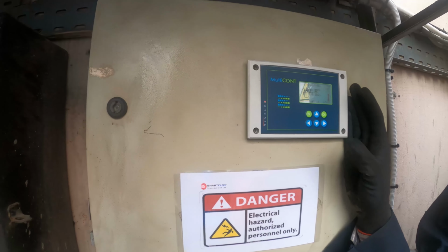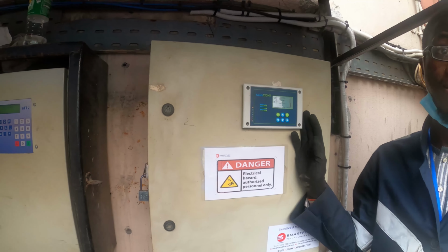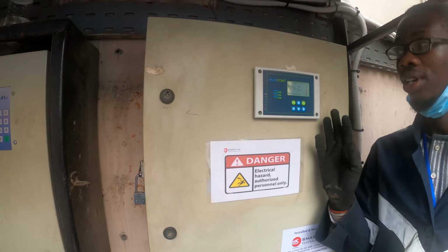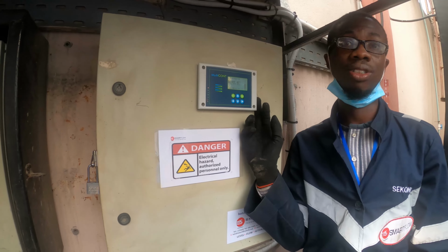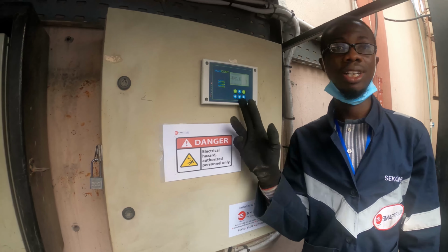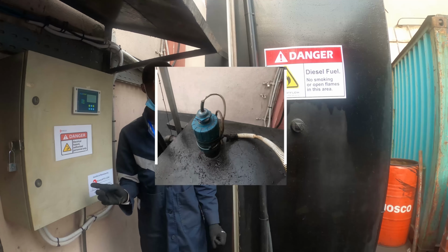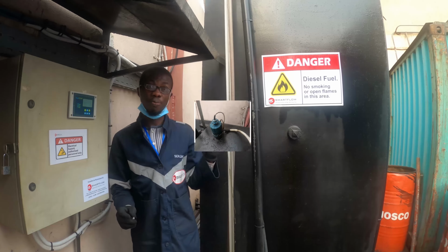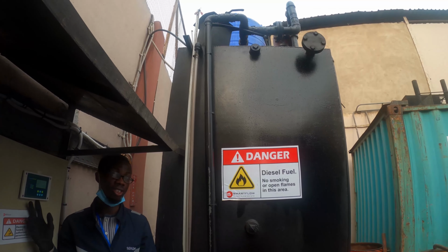This system is also linked to our remote monitoring platform, which we call SmartEye. We are consistently having logs from this system on a 2 minute interval. So at any point in time, the user can log in, check his tank level, and see what he actually has in there. My ATG is connected to a probe we have on this tank here. The sensor is what is actually monitoring the fuel volume, and it's constantly giving the ATG console here that value.